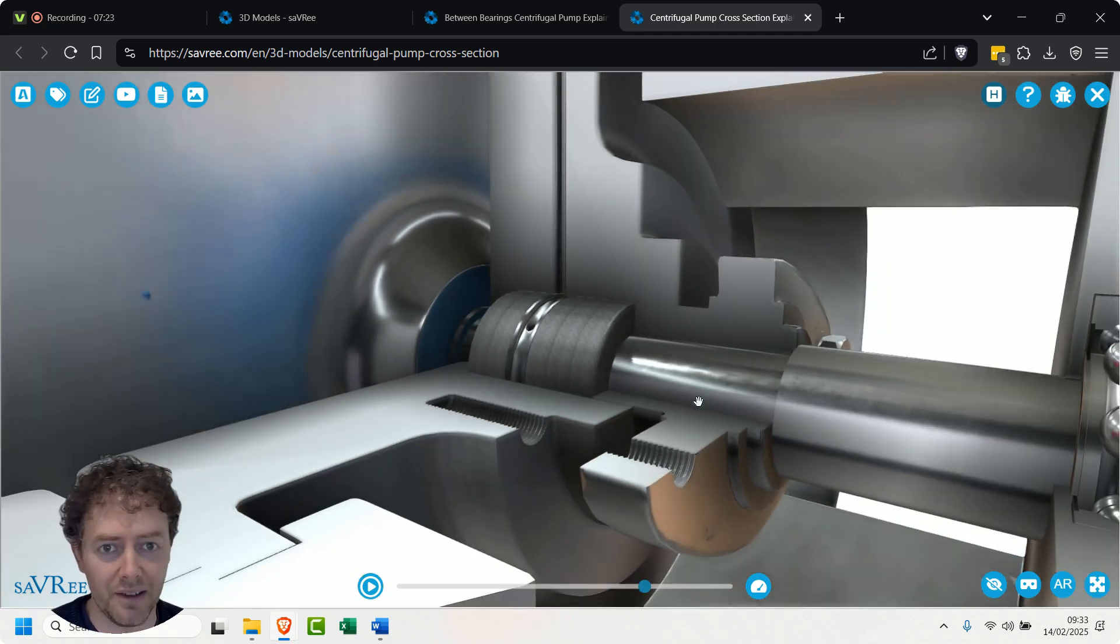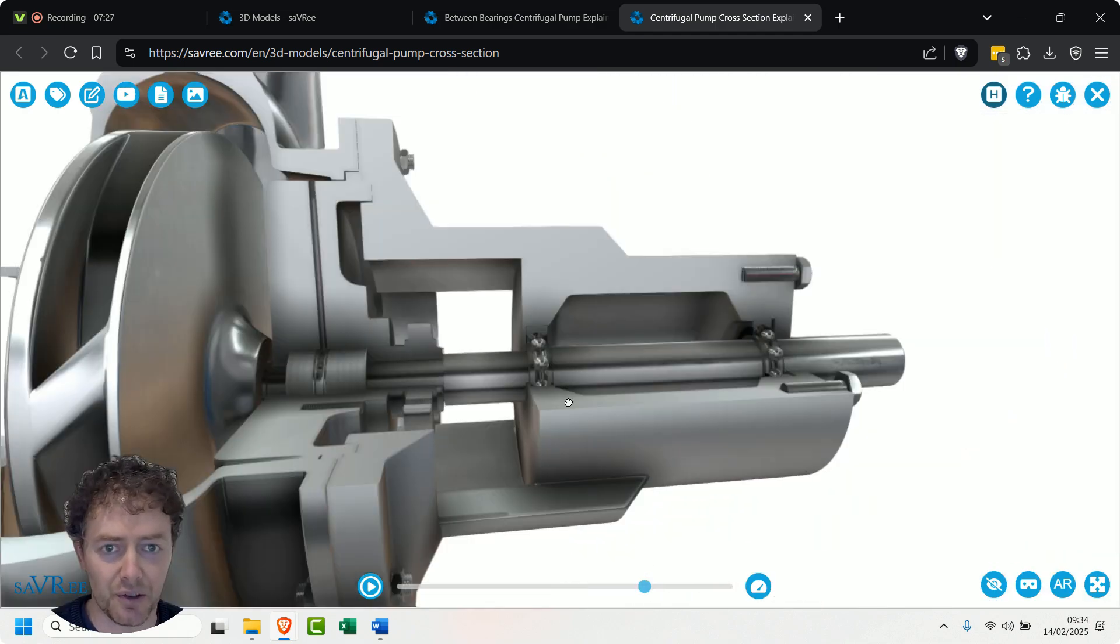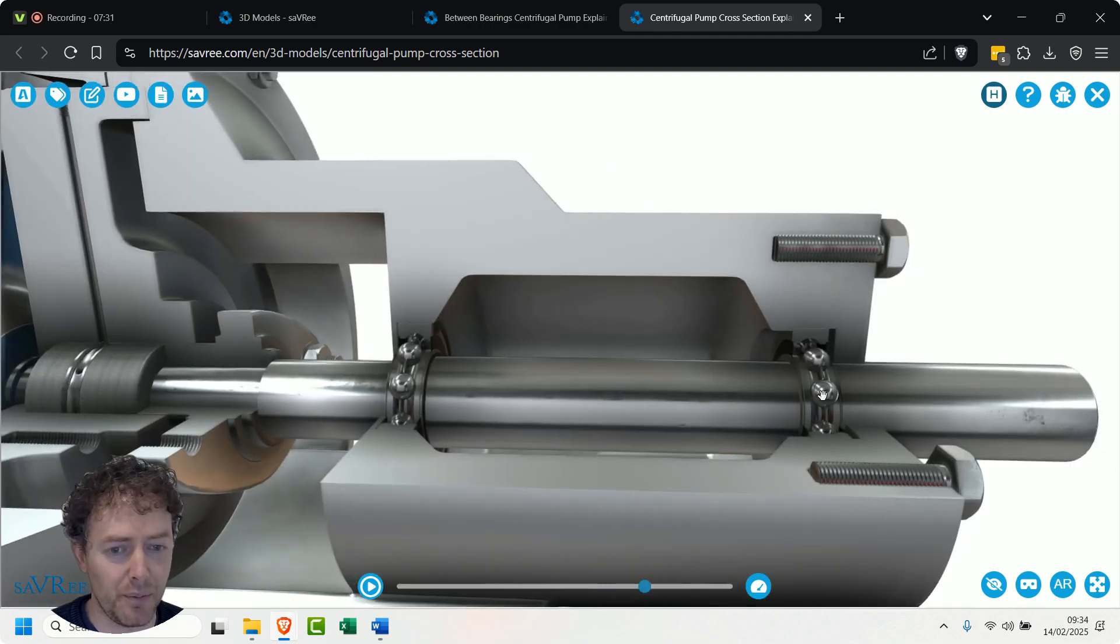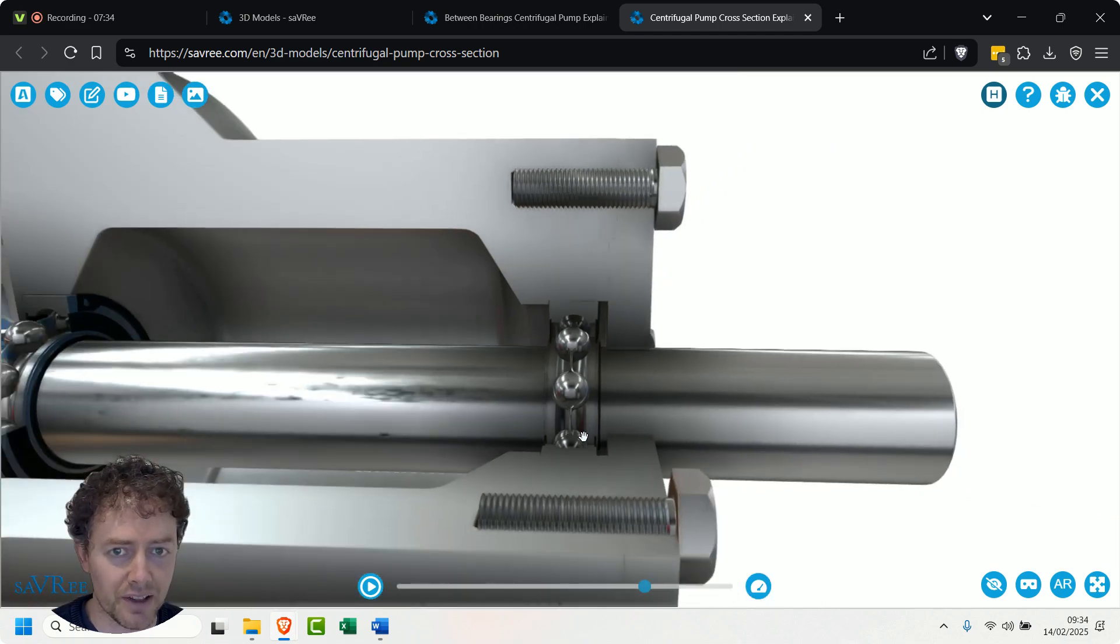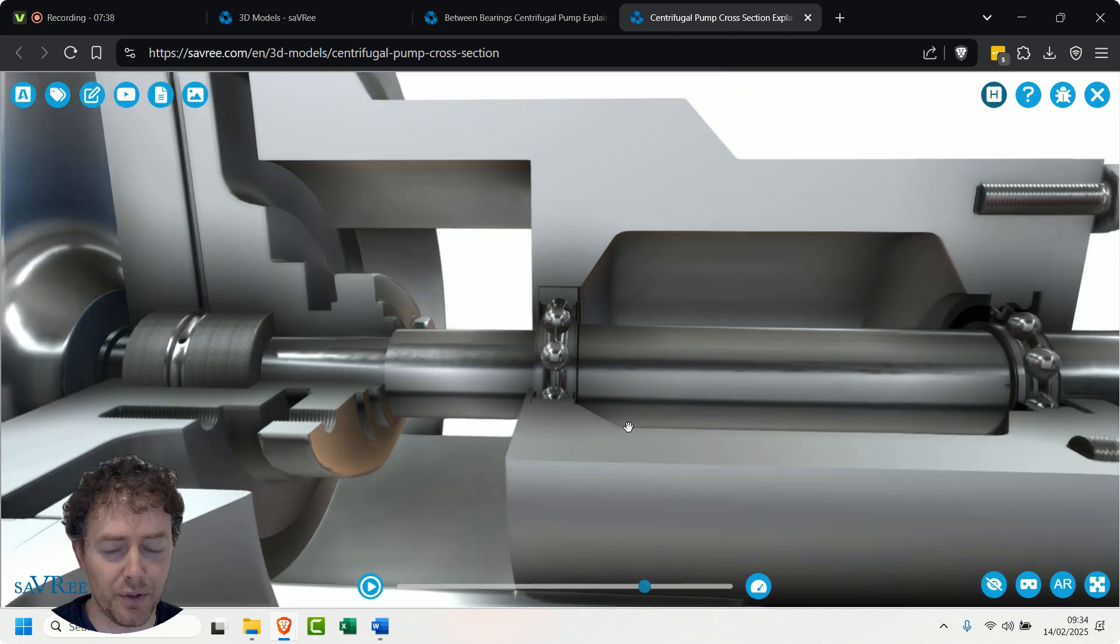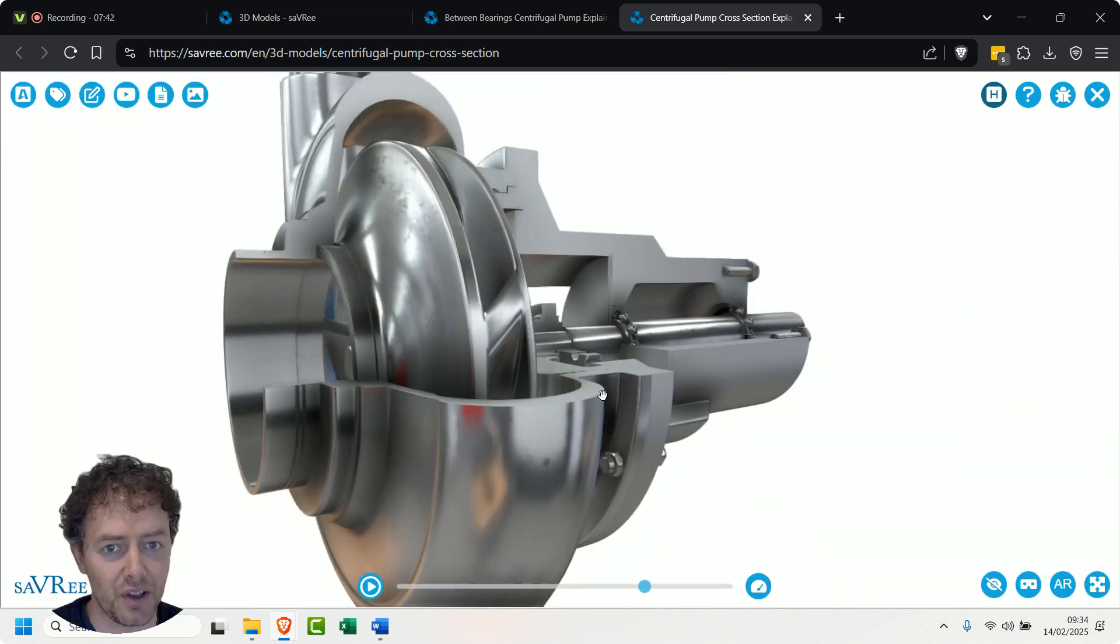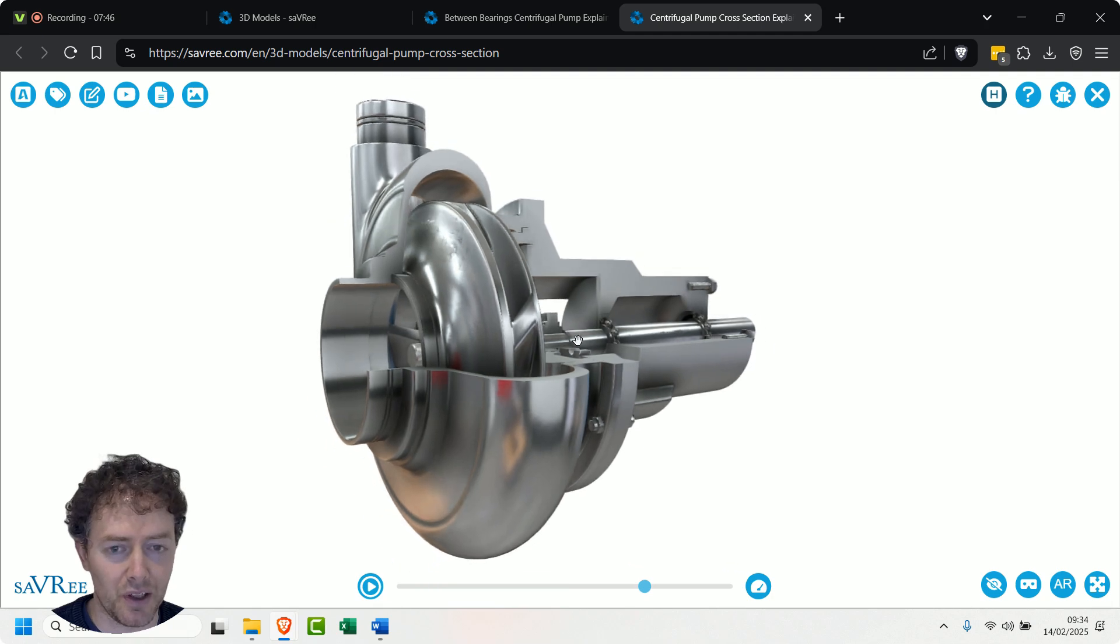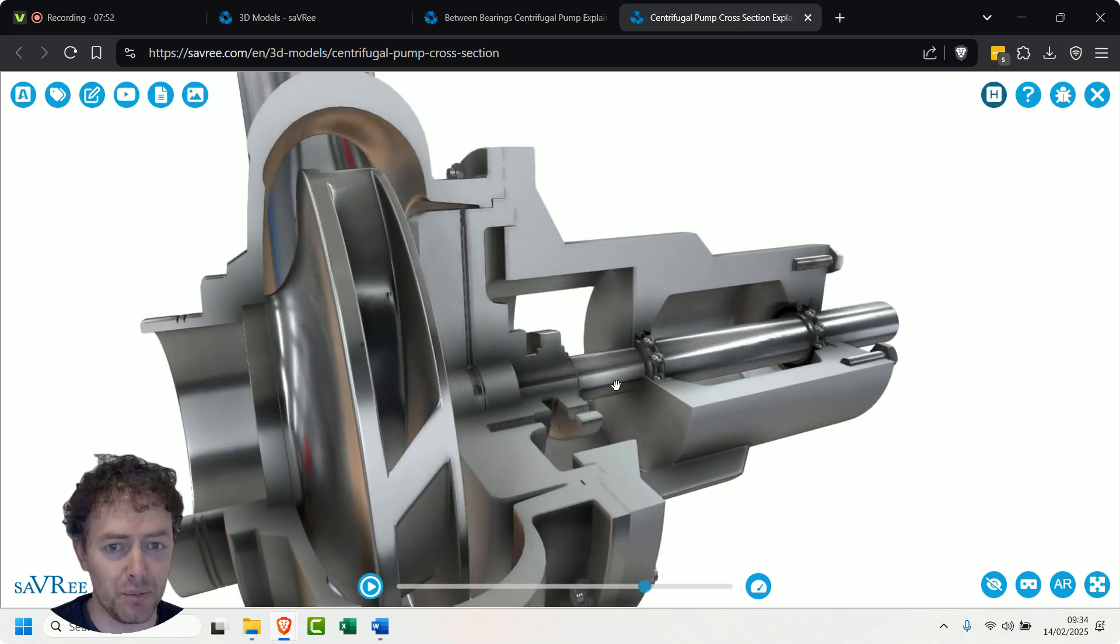It's a common way to damage the pump and it happens quite a lot, I'll be honest. The other things that you're going to pay attention to on this pump are the bearings. And you may have different type of bearings here - these are ball bearings, also known as anti-friction bearings. It depends though on the pump design, because if you're dealing with thrust, if you're dealing with a lot of that, then you may use different style of bearings. If the impeller is quite large, you may use different style of bearings as well, because ball bearings - they're good, they're good all-round bearings, but sometimes you might need cylinders instead of balls, and then yeah, it's a different type of bearing entirely.